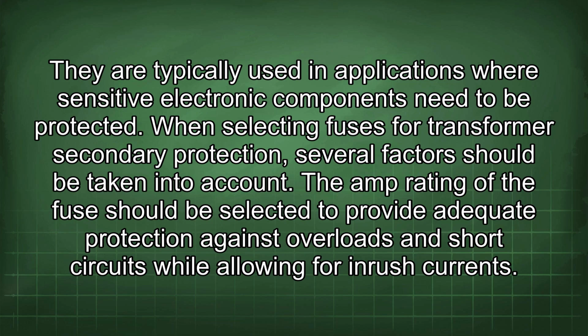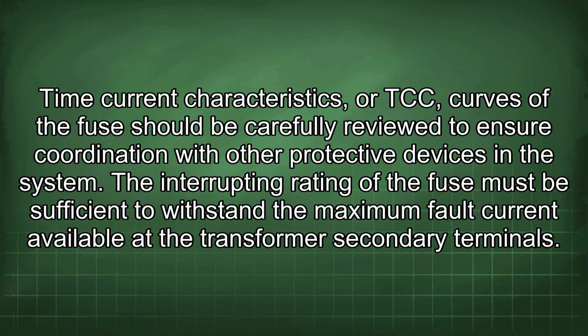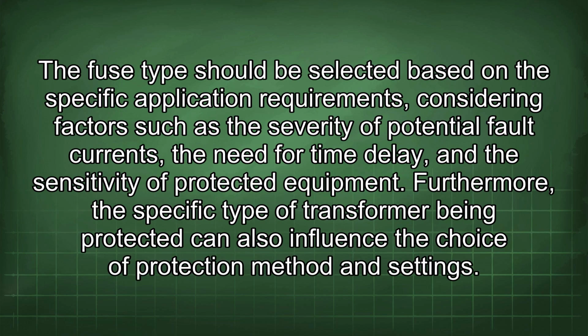The amp rating of the fuse should be selected to provide adequate protection against overloads and short circuits while allowing for inrush currents. Time current characteristics, or TCC curves, of the fuse should be carefully reviewed to ensure coordination with other protective devices in the system. The interrupting rating of the fuse must be sufficient to withstand the maximum fault current available at the transformer secondary terminals. The fuse type should be selected based on the specific application requirements, considering factors such as the severity of potential fault currents, the need for time delay, and the sensitivity of protected equipment.